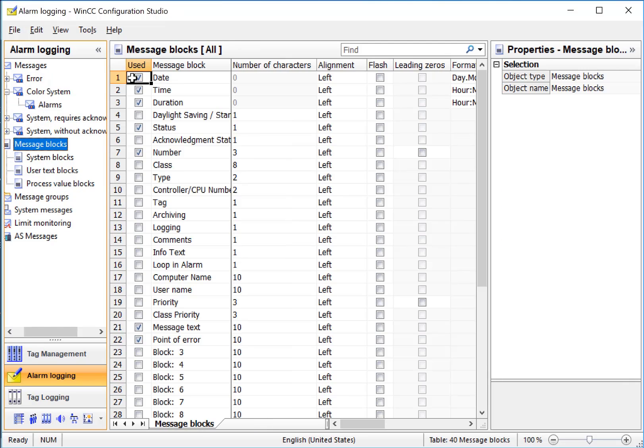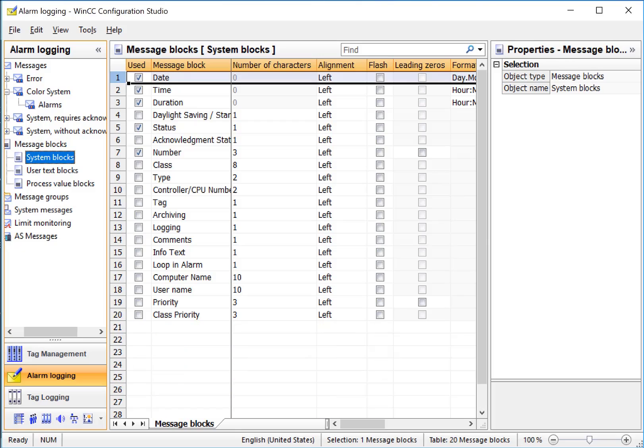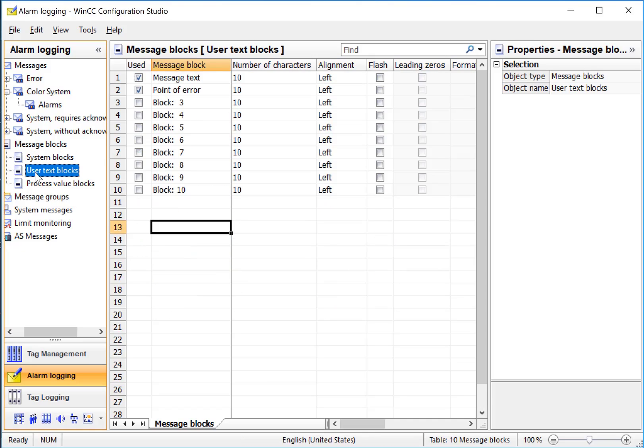Under Message Blocks, we see that we have different types of information that we can add to our alarm system. System Blocks are data that is coming from this SCADA system, like date, time, status, and duration, and you can just check the ones you want now or you can do it later. Under User Text, these are message blocks that contain text, which is customized for each alarm message, and these are things that the user sees when alarms occur.